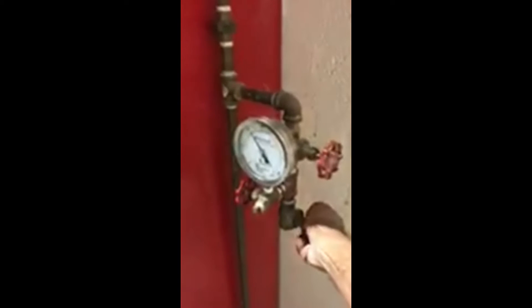Next to each control panel there are two valves with a pressure gauge. You can see the pressure. Open this valve here if you want to check the jockey pump first, then close it back up. Shut this off, and if you want to turn the main pump on, just open this test valve.